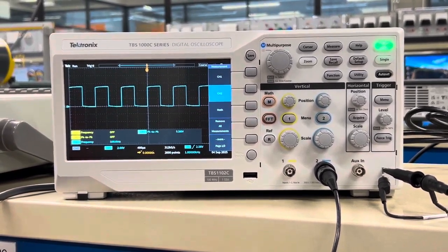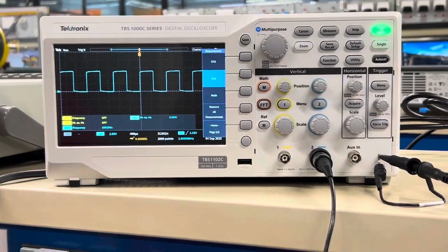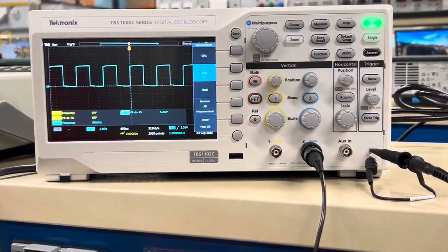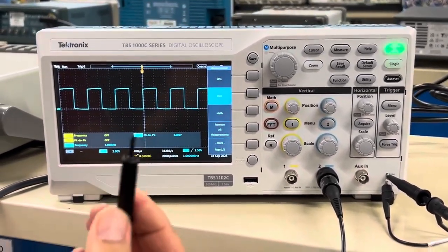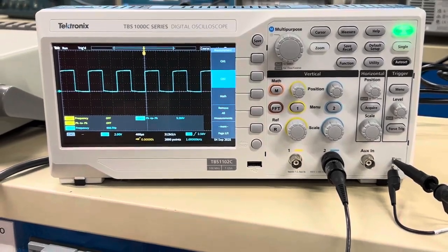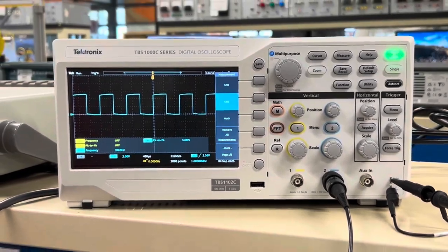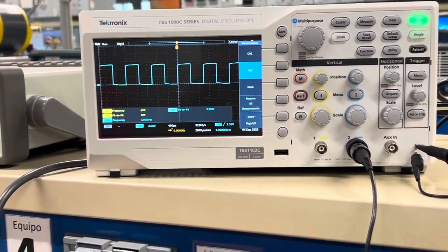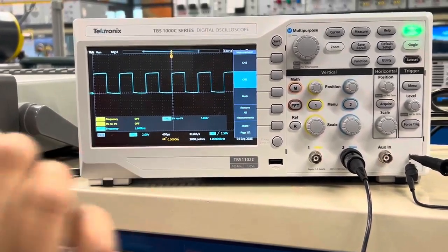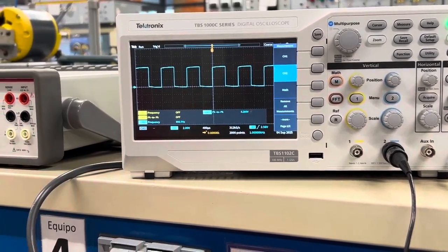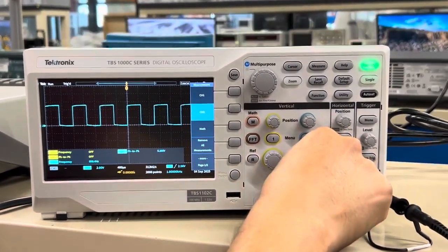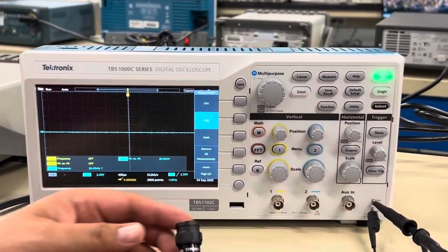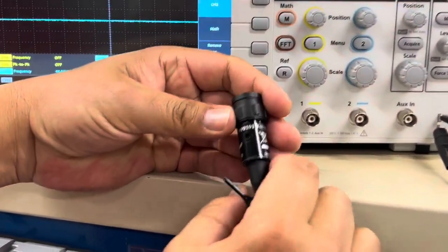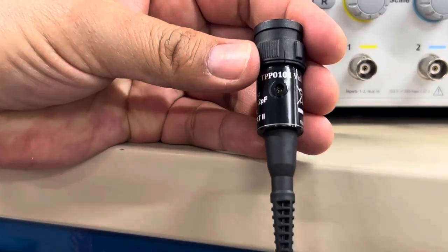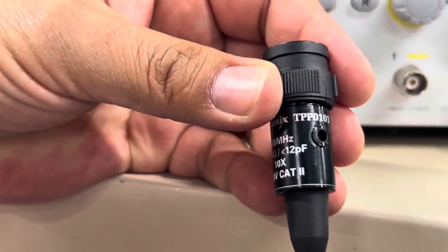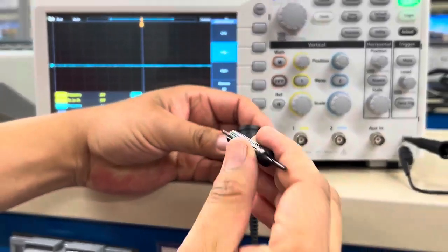So the probe is working, but it's not working as properly as the other probe. So we'll bring this screwdriver and we will calibrate the coupling capacitance of this probe. We will get the flat end of this screwdriver, which is especially tailored for this purpose. I'm going to disconnect the probe quickly. And there is a hole in the body of the BNC connector. I hope that you can see it. I think you do.